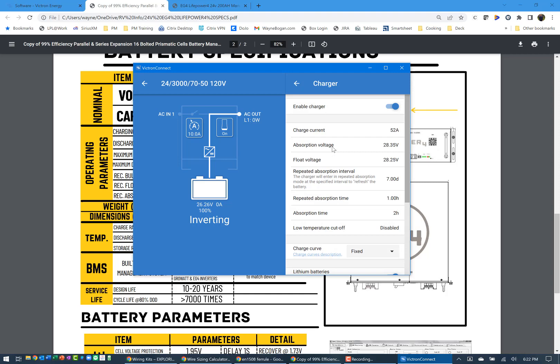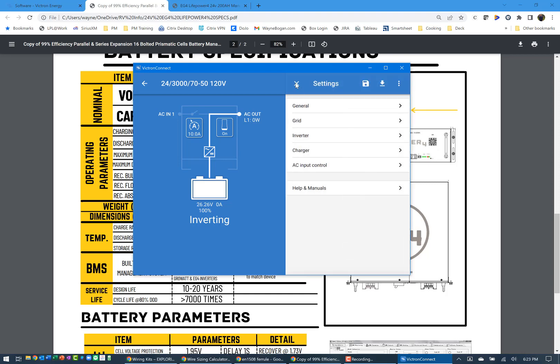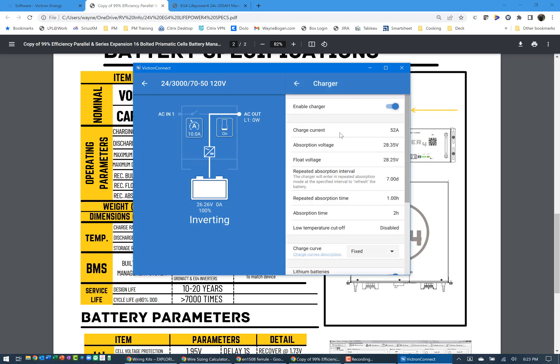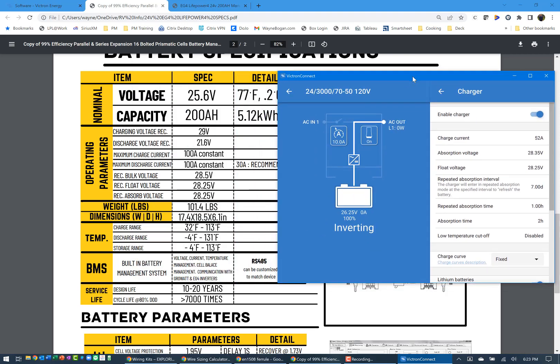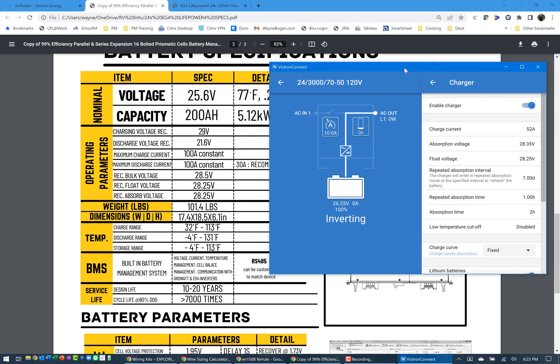For the charger, so you come into charger, we're going to enable the charger because we do want it to charge the batteries. It is set up to 52 amps coming back in for the battery, right? And you can go back and look. The maximum current charge on these batteries are 100 amps. So I'm actually good on that side. I'm going to leave this at 52. Then I'm going to come back and I'm going to change these two settings.